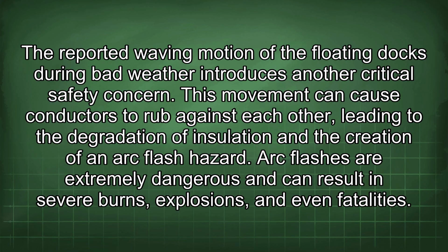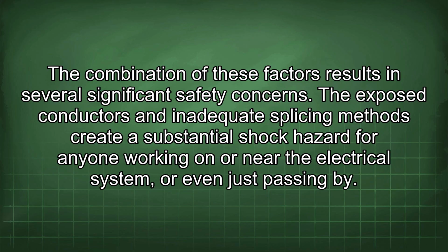This movement can cause conductors to rub against each other, leading to the degradation of insulation and the creation of an arc flash hazard. Arc flashes are extremely dangerous and can result in severe burns, explosions, and even fatalities. The combination of these factors results in several significant safety concerns. The exposed conductors and inadequate splicing methods create a substantial shock hazard for anyone working on or near the electrical system, or even just passing by.